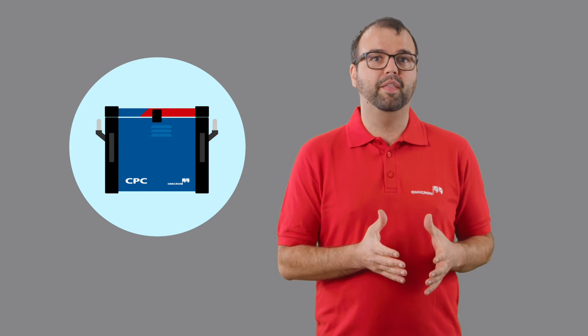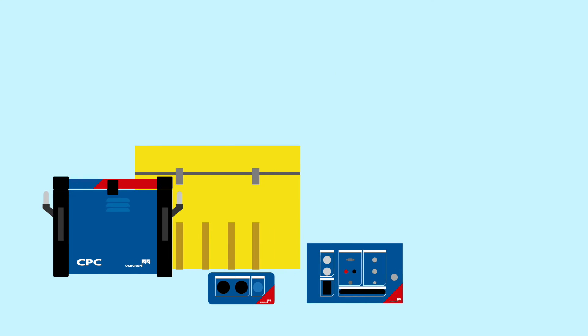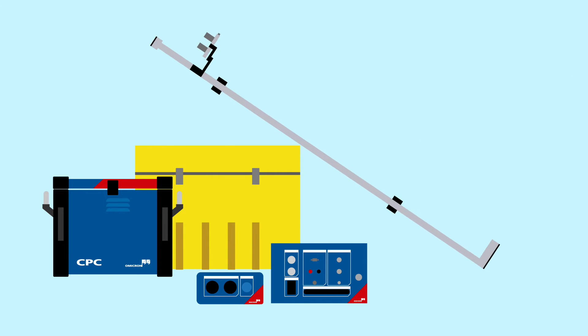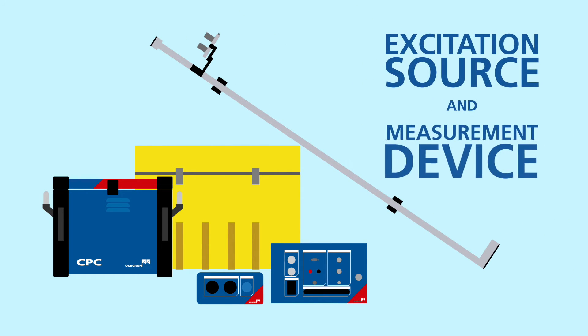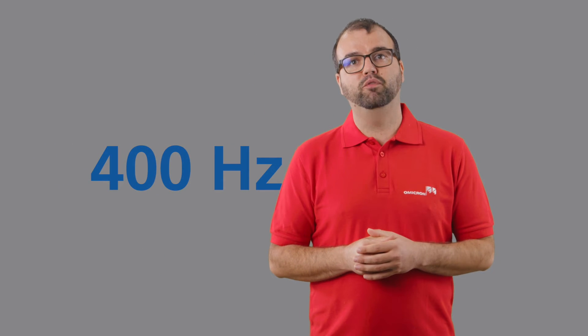Enough power out of an ordinary power plug in combination with a high accurate in and output allows the CPC-100 to act as both the excitation as well as the measurement device. This gives us the possibility to test either with rated frequency 50 or 60 hertz or frequencies even up to 400 hertz.